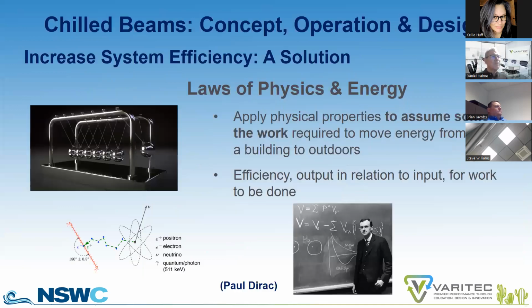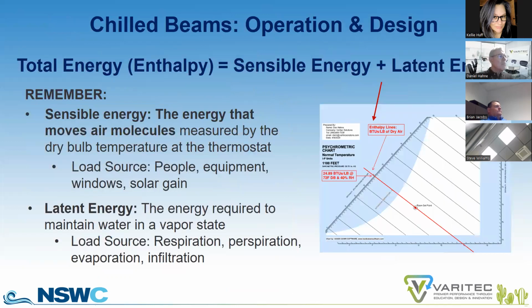Let's look at the overall concept, how they operate, and some design considerations. One of the aspects I find very compelling about sustainable heating and ventilating systems is that instead of calculating the amount of energy required to move heat from point A to point B, it allows us to exploit the physical properties of heat transfer mediums and radiation to execute some of that work for us, so we don't need supplemental energy to do that. So before we expand upon this thought, let's again review total energy. Total energy, also known as enthalpy, is equal to the sensible energy in a building as measured at a thermostat, and the latent energy, the energy to hold water in a vapor state.